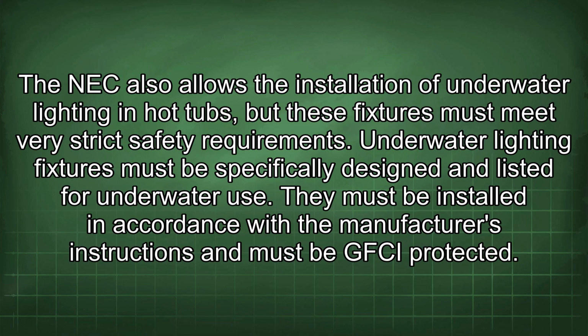The NEC also allows the installation of underwater lighting in hot tubs, but these fixtures must meet very strict safety requirements. Underwater lighting fixtures must be specifically designed and listed for underwater use. They must be installed in accordance with the manufacturer's instructions and must be GFCI protected.